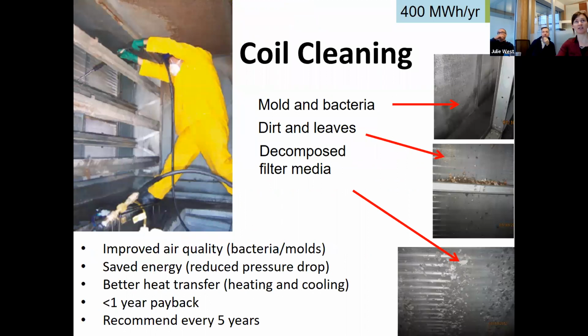The next thing we did is a coil cleaning program, and we did this not just in life sciences, but campus-wide throughout all of our large air handling units. So we hired some cleaners to come in and clean the coils, remove the mold and bacteria, dirt and leaves, decomposed filter media. It was pretty grimy looking. This also had a less than 1 year payback and is recommended every 5 years. So I think it's been around 10 years, and we are just looking at doing this again. And our original M&V showed that we saved roughly 400 megawatt hours per year, 1% of the building's energy consumption. And this is through reduced static pressure drop, basically, and allowing for increased heat exchange from the coils.